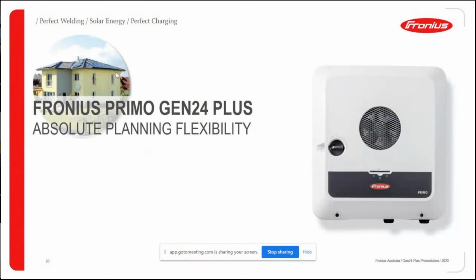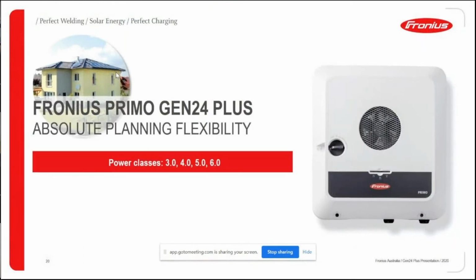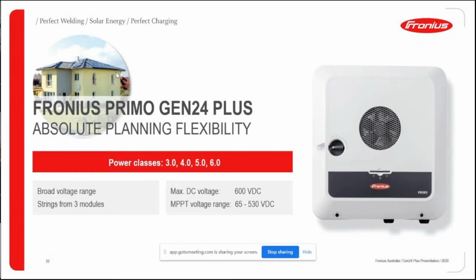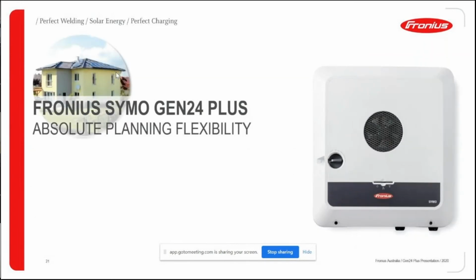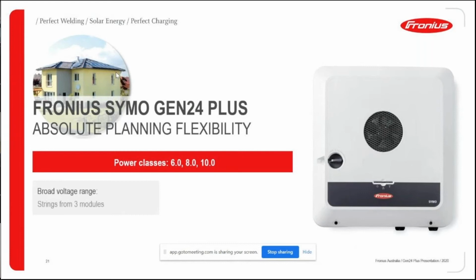All right, so just moving along, the Gen24s have a very wide MPPT voltage range, so it's going to be very easy to design your PV array. Designing your strings for your customer's rooftop is going to be very easy because you've got a wide voltage range. You can see you've got down as low as 65 volts and up to 530 volts DC on the MPPT for the Primos, and 22 amps on one input and 12 amps on the second input. And then it's the same with the Symos. In the Gen24s, you've got a slightly different voltage range. You've got 80 volts all the way up to 800 volts DC with the Symos.